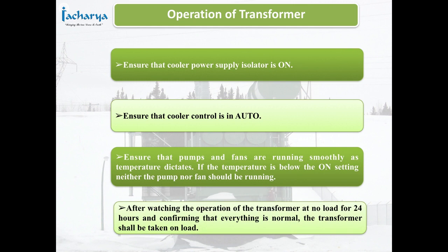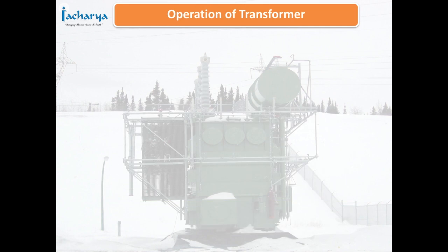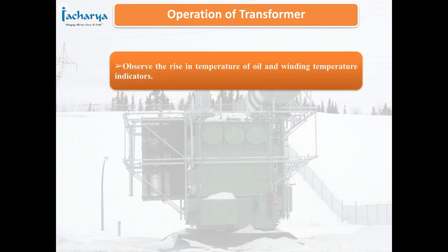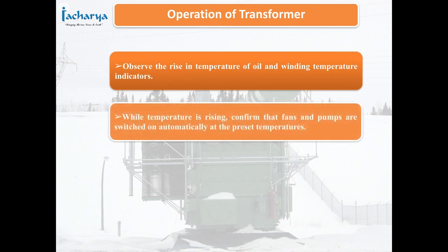After watching the operation of the transformer at no load for 24 hours and confirming that everything is normal, the transformer shall be taken on load. Observe the rise in temperature of oil and winding temperature indicators. While temperature is rising, confirm that fans and pumps are switched on automatically at the preset temperatures.